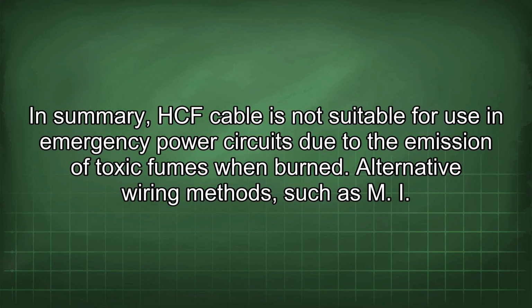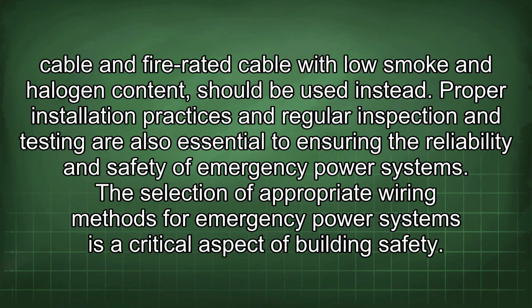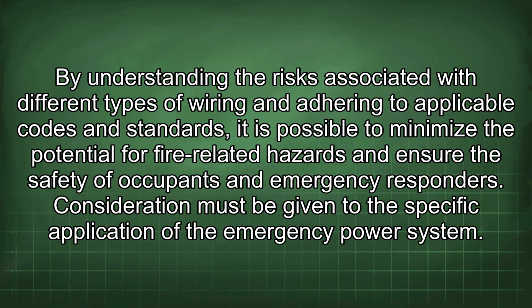In summary, HCF cable is not suitable for use in emergency power circuits due to the emission of toxic fumes when burned. Alternative wiring methods such as MI cable and fire-rated cable with low smoke and halogen content should be used instead. Proper installation practices and regular inspection and testing are also essential to ensuring the reliability and safety of emergency power systems. The selection of appropriate wiring methods for emergency power systems is a critical aspect of building safety. By understanding the risks associated with different types of wiring and adhering to applicable codes and standards, it is possible to minimize the potential for fire-related hazards and ensure the safety of occupants and emergency responders.